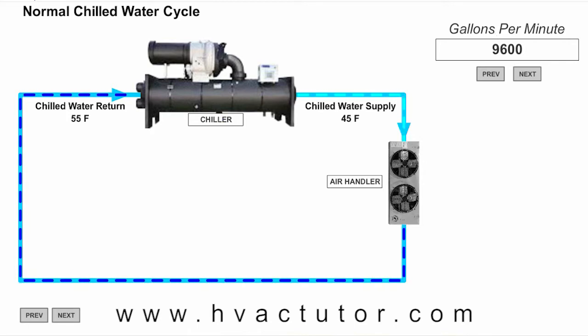We're circulating 9,600 gallons per minute. The temperature difference is going to be 10 degrees. Each gallon weighs 8.33 pounds. That will give us close to 80,000 pounds of water per minute. If I have roughly 80,000 pounds per minute and I'm cooling it 10 degrees and the specific heat is 1, then the chiller needs to remove roughly 800,000 BTU every minute. That is going to give me close to 4,000 tons of cooling.